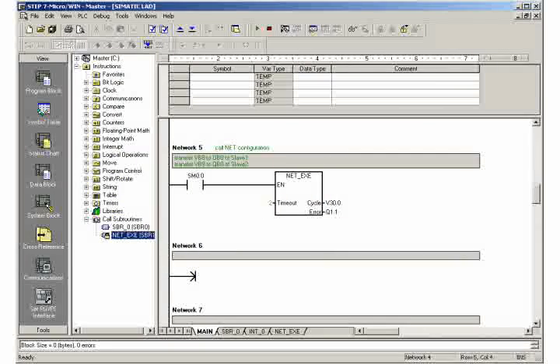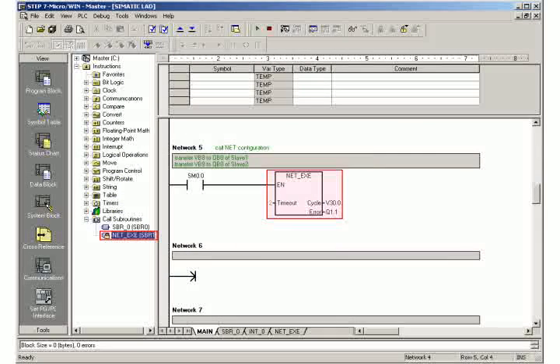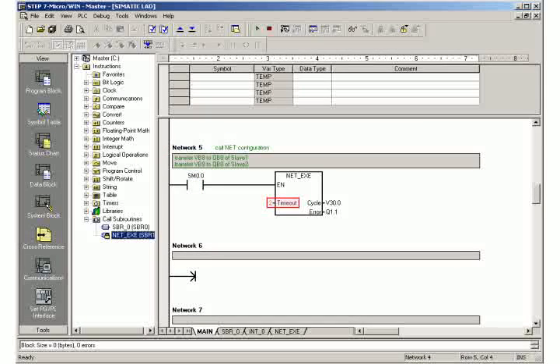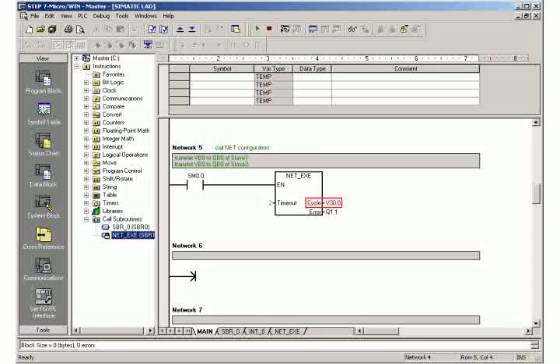Call the subroutine NET_EXE generated by the instruction wizard every scan cycle in network 5. As timeout, select 2 seconds, assign a free variable address for the cycle bit, and display communication errors at output Q1.1.